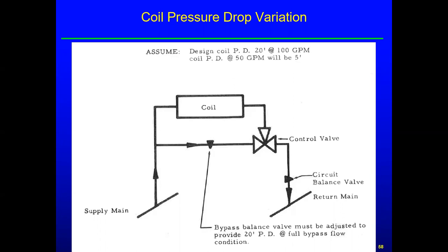And we show down at the bottom the note, the bypass valve must be adjusted to provide 20-foot pressure drop at full bypass flow. So that makes it simulate the coil. It has the same flow, pressure drop characteristics as the coil. So this is an issue.